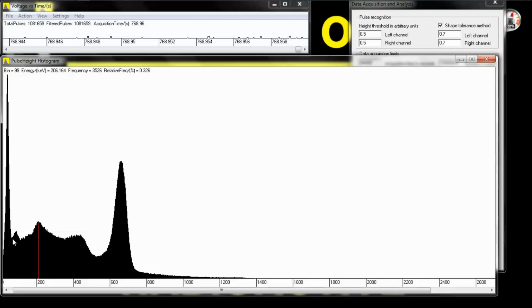And this peak right here comes from the actual lead shielding around the detector, and it should be somewhere around 75 to 80 kiloelectron volts. And that's exactly where it is. All right, so we are effectively calibrated. We could be better calibrated than we are, but this is a basic calibration. We know the detector's pretty much working. So let's take that soil now, put it in the detector, run it for a short time, see what's in it. That'll be fun, won't it?